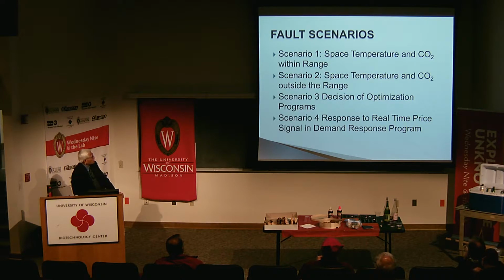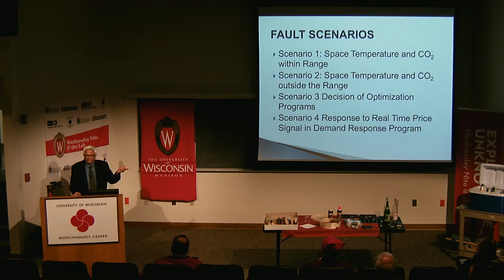And the second scenario for fault is, CO2 may be okay, but space temperature is outside the range. Why is it so? The third is, we discussed optimal start, optimal stop. How do you know they are not at fault? They are not faulty. And if they are faulty, what kind of a penalty do they impose on the cooling system? So we will address that. The last one is response to real-time pricing. If there is a fault in the lighting when you want to shed the lighting load, then it affects the demand response program. I won't go into detail for that because I already covered enough on the demand response part.